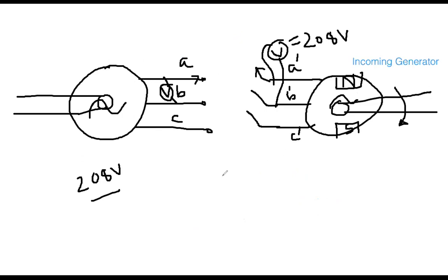Now come back to the phase sequence. You have to meet all of those four conditions. So how would you understand that this A phase, B phase, C phase, and here A phase, B phase, C phase, have the same sequence? How would you understand that this is not ACB, or this is not ACB? How can you verify that? You must verify that.